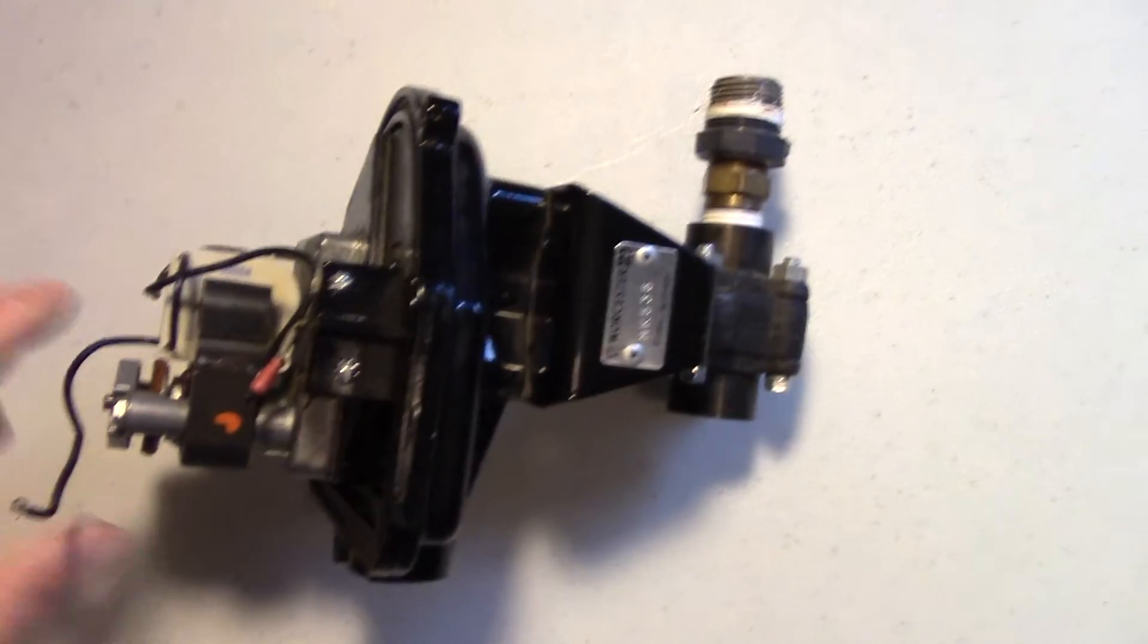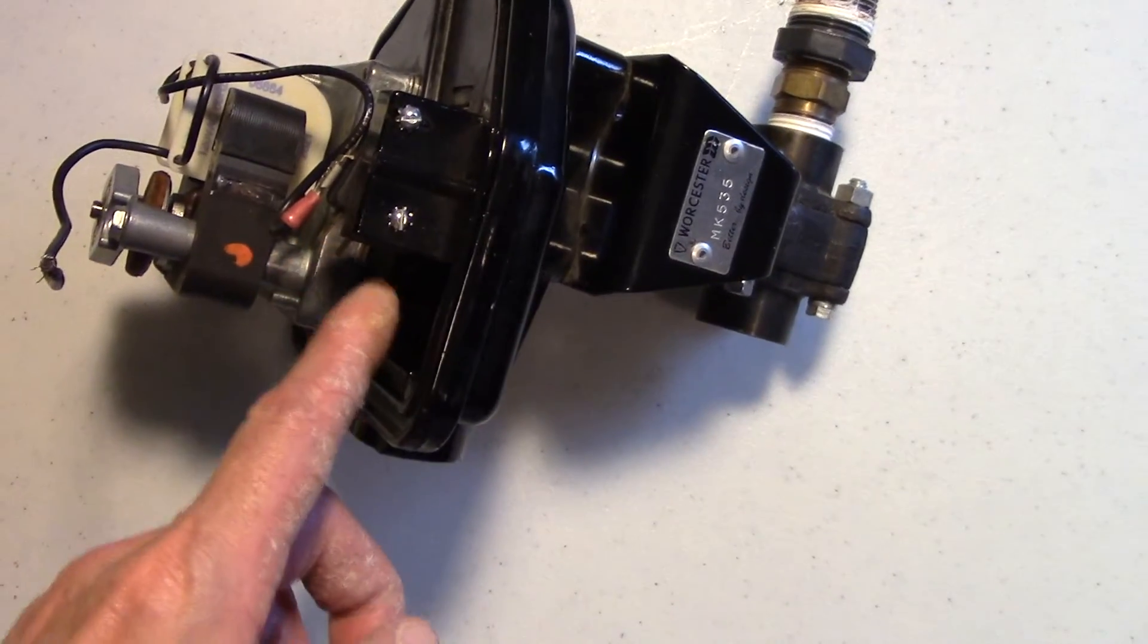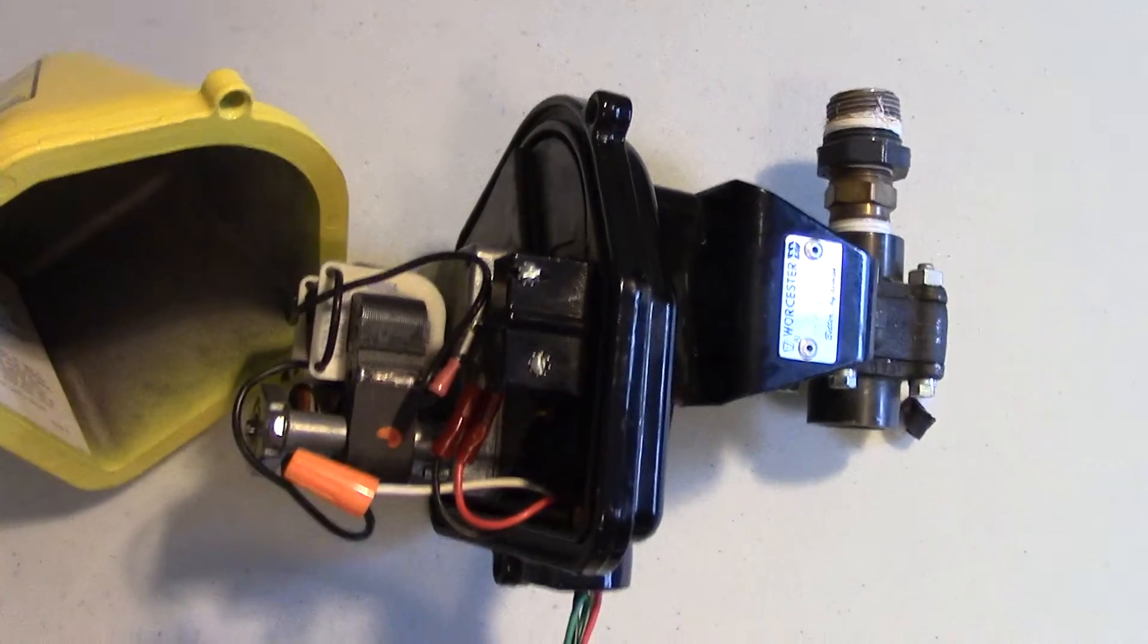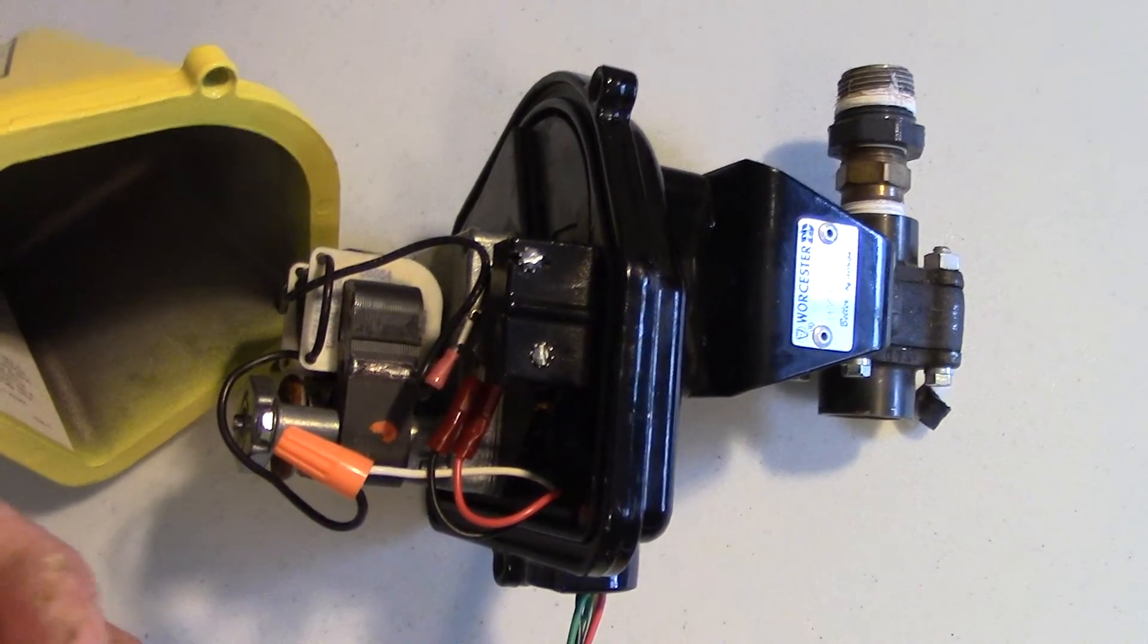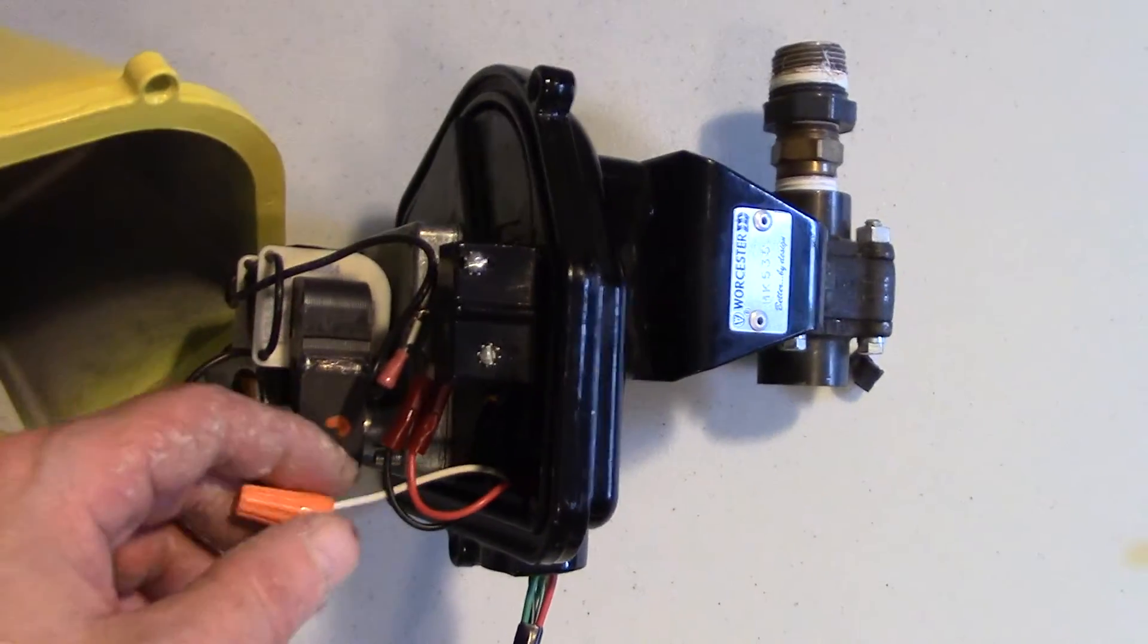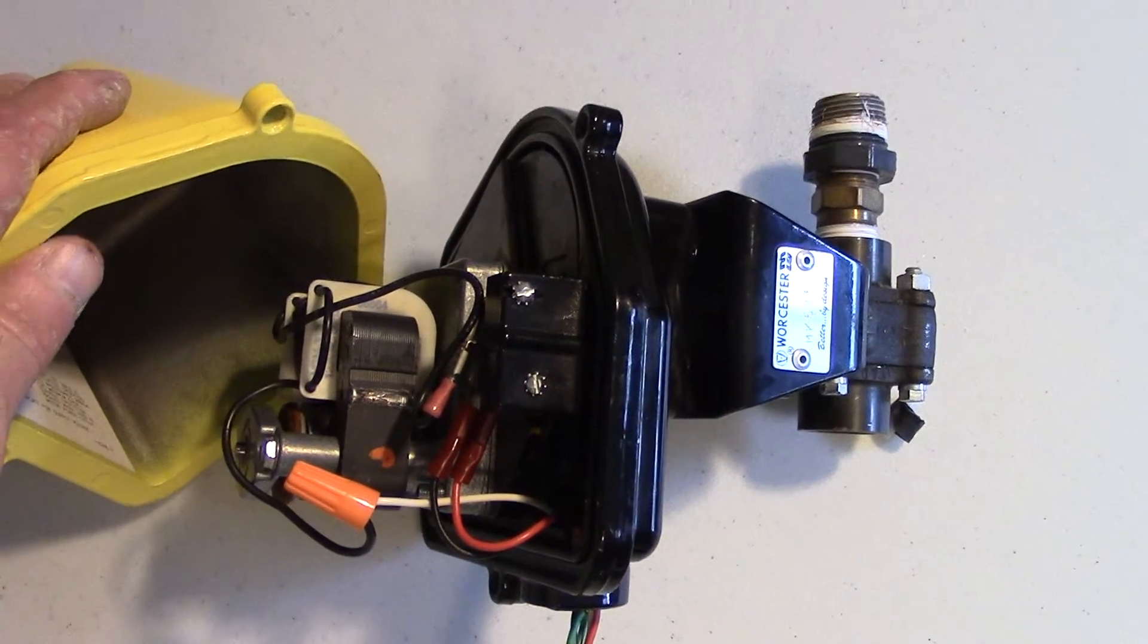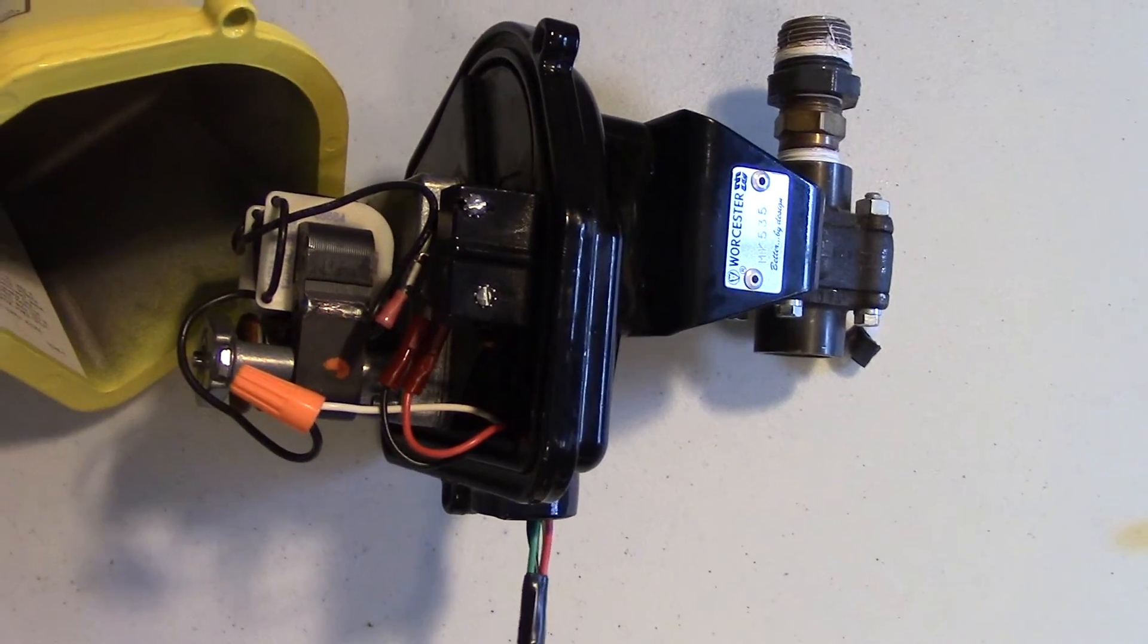Now I know from the wiring diagram that this is a neutral wire and here's where you land the two hot wires that will be going back to the controller. So what I did is I made a wiring harness since the valves typically don't come with extension cable or extension wires. And I wired up the valve in accordance to the wiring diagrams from the manufacturer. And then I run the rest of the harness back to the controller.